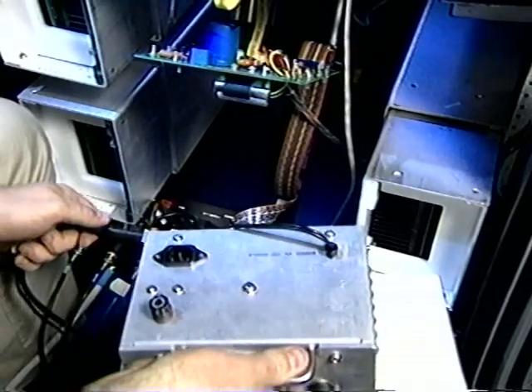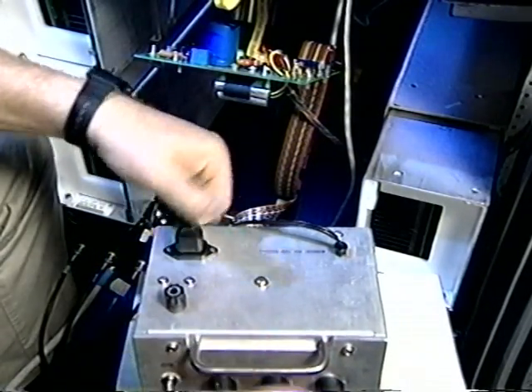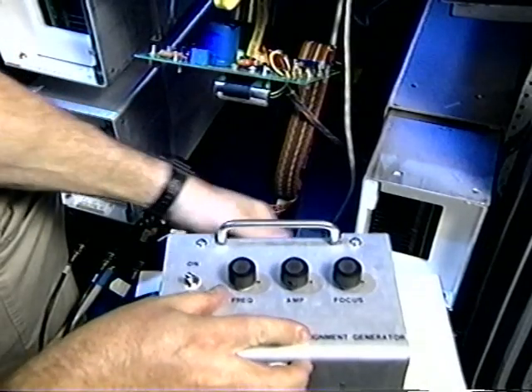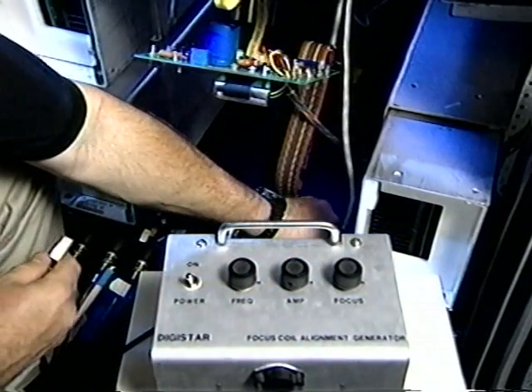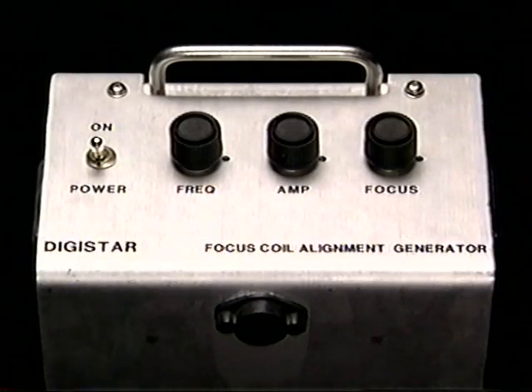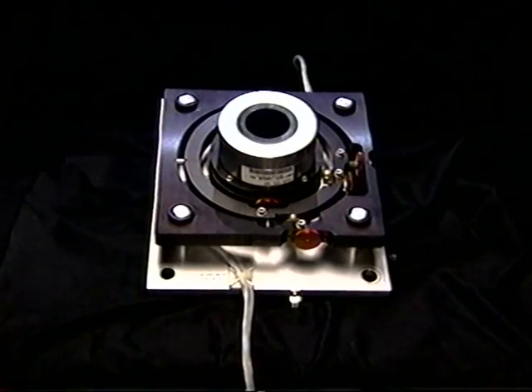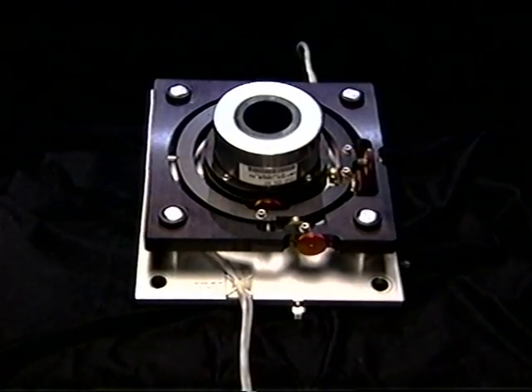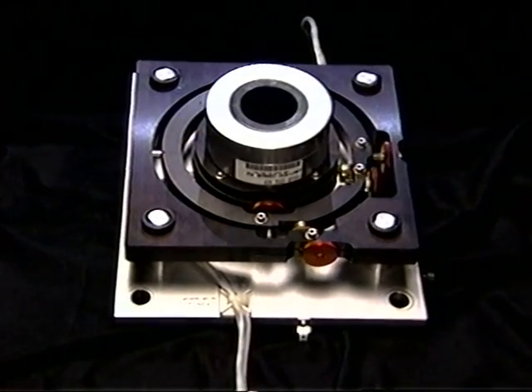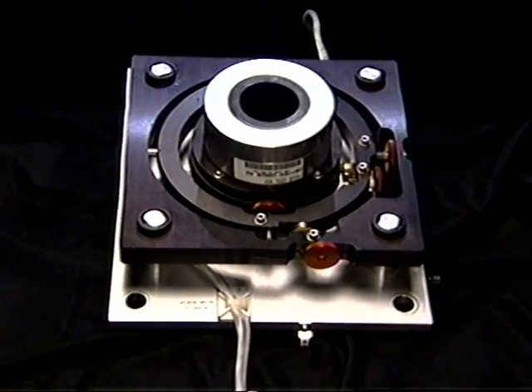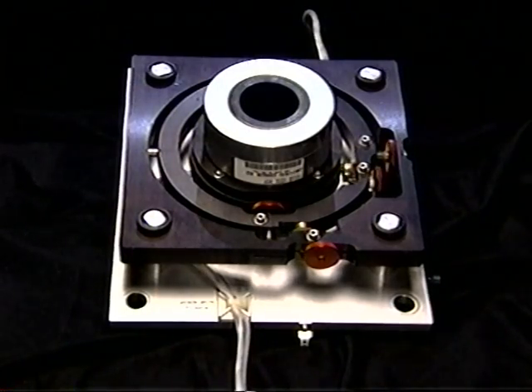A special piece of test equipment known as the jitter box is used to align the coil. The jitter box temporarily replaces the static focus coil power supply in the power drawer. The jitter box has 3 knobs. Focus. This knob sets the DC offset. It operates the same as static focus. Amplitude. This knob sets the amplitude of focus variations. Frequency. This knob sets the rate at which the focus varies. The technician aligns the focus coil by turning knobs on the micropositioner while observing the projected image. When the image is correct, the jitter box is disconnected and the focus coil is reconnected to the static focus power supply.